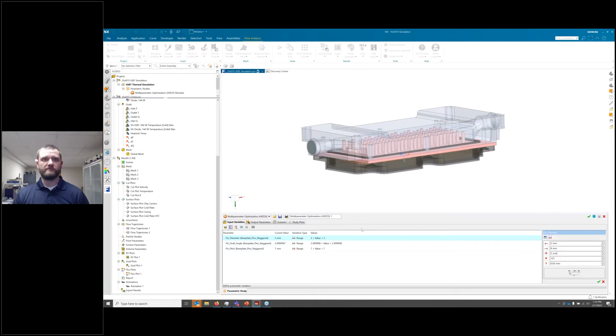So we would define all our constraints here. In our output parameters, we would just use our goals. In this case, maybe we want to look at the pressure drop and the IGBT temperature, so we could select those, and then we could select a bound for each one of those. So the constraint for the IGBT would be an upper bound of maybe, let's say it has to be less than 95 degrees C. And we would also do the same thing for the pressure drop, limiting it to a maximum value so that the study wouldn't go outside that range.